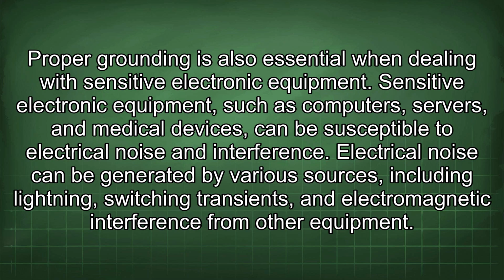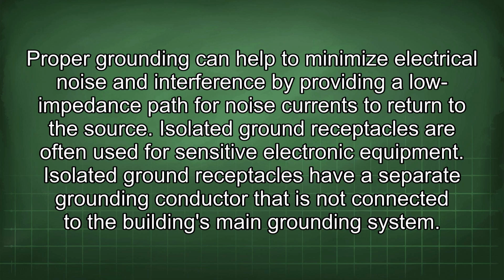Proper grounding is also essential when dealing with sensitive electronic equipment. Sensitive electronic equipment, such as computers, servers, and medical devices can be susceptible to electrical noise and interference. Electrical noise can be generated by various sources, including lightning, switching transients, and electromagnetic interference from other equipment. Proper grounding can help to minimize electrical noise and interference by providing a low impedance path for noise currents to return to the source.